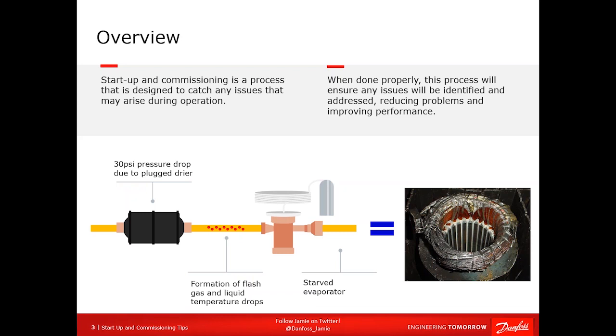Let's think about it for a second. If you're replacing a compressor that failed, it failed for a reason. If you just replace the compressor, charge the system, and miss the issues that caused this compressor to fail, that compressor has a really good chance of failing again. So you have to take a step back and look at the system beyond just the compressor and find these underlying causes. You can see there's a dead compressor here that burned up, and this is a real example. It was a blockage in the liquid line that starved the compressor, overheated it, and we had a failed compressor.